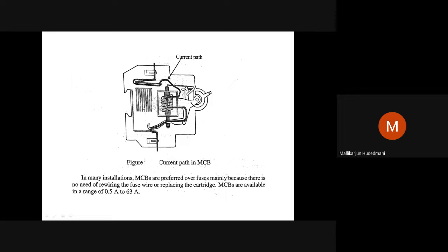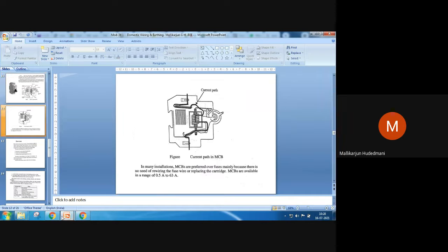This is a small window which will have quenching of the arc, because when the current is flowing through this device, due to that overcurrent, let's say it has tripped, operated, there could be a spark here. That spark or arc definitely makes some smoke-like fumes come. Those fumes are quenched here. That is going to just arrest them. It will collect the fumes and get them out. This way, a small arc chamber like assembly is made here. I'll show the physical structure of that also. I have another diagram which will show you the physical structure of that.